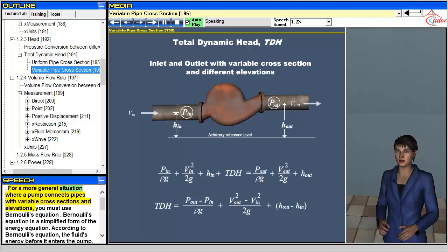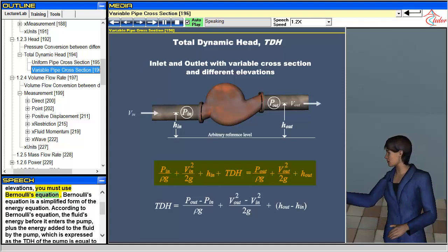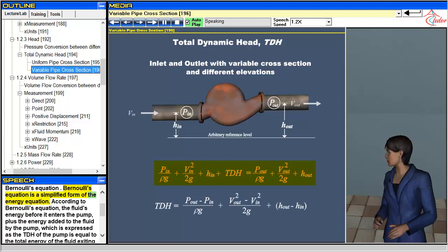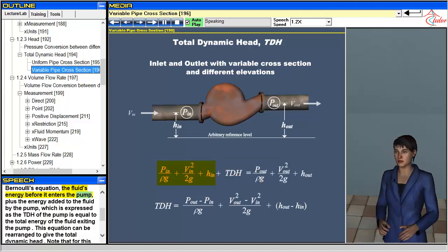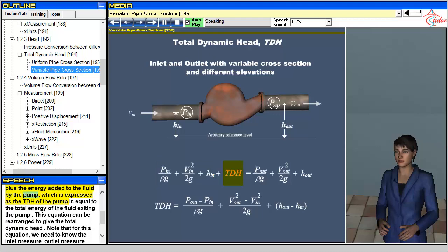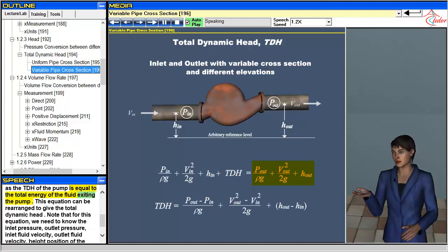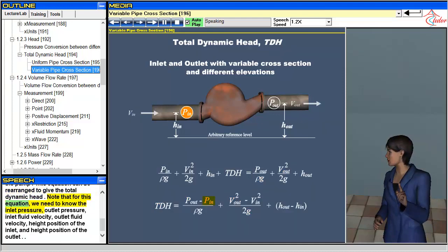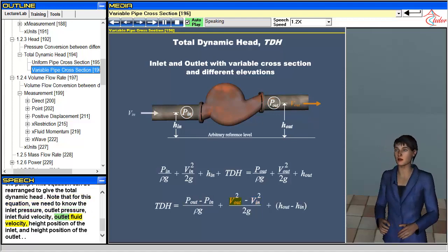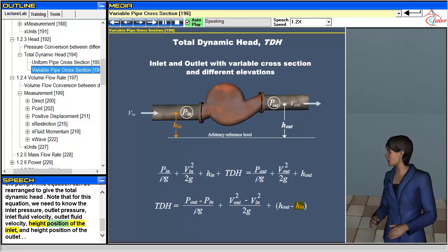For a more general situation where a pump connects pipes with variable cross sections and elevations, you must use Bernoulli's equation. Bernoulli's equation is a simplified form of the energy equation. According to Bernoulli's equation, the fluid's energy before it enters the pump, plus the energy added to the fluid by the pump, which is expressed as the TDH of the pump, is equal to the total energy of the fluid exiting the pump. This equation can be rearranged to give the total dynamic head. Note that for this equation, we need to know the inlet pressure, outlet pressure, inlet fluid velocity, outlet fluid velocity, height position of the inlet, and height position of the outlet.